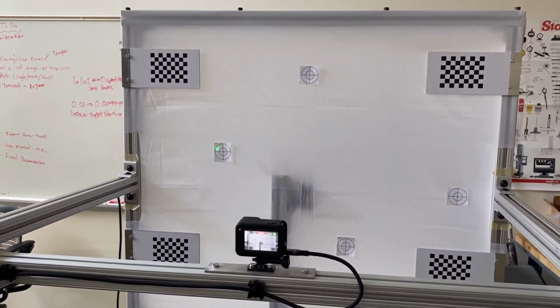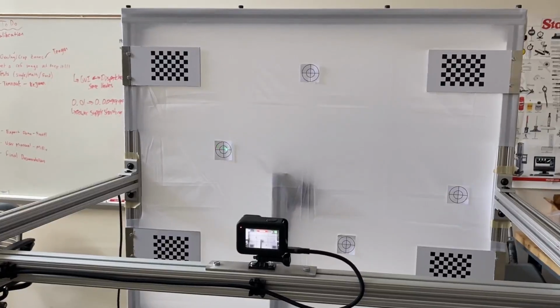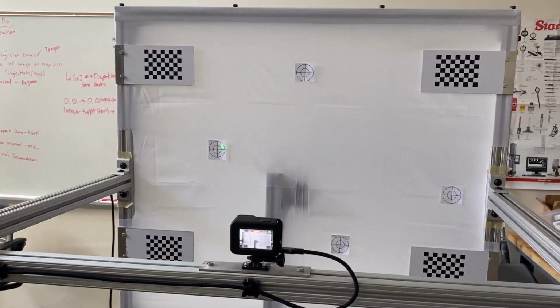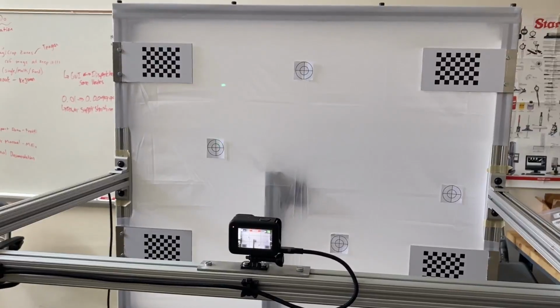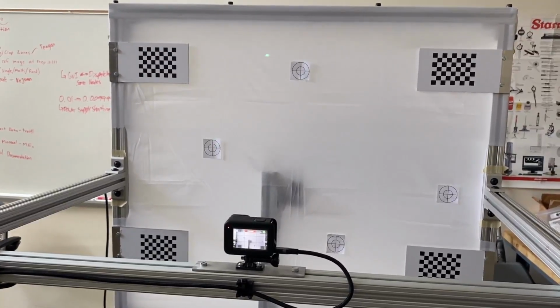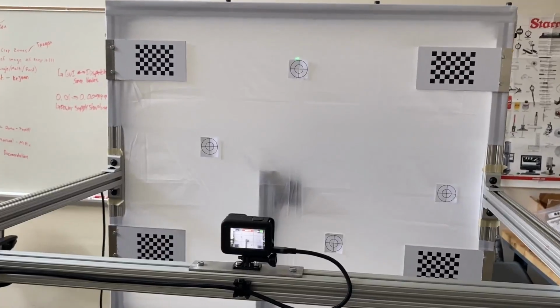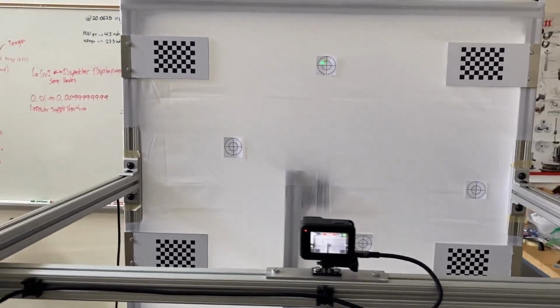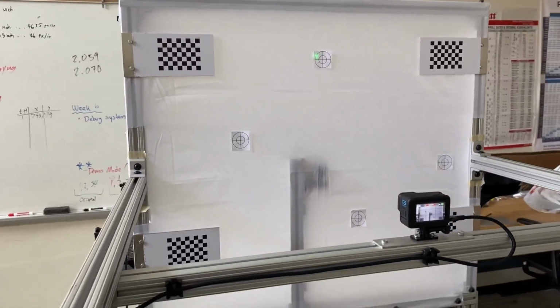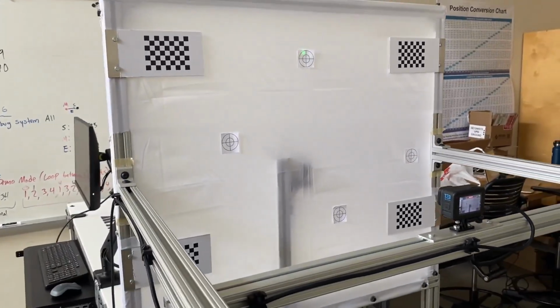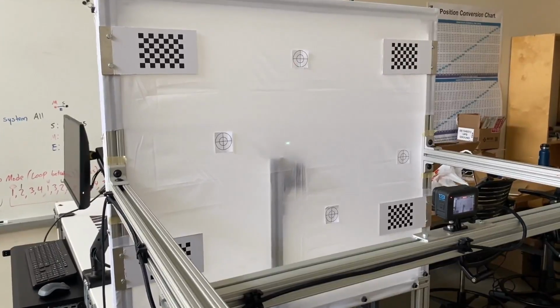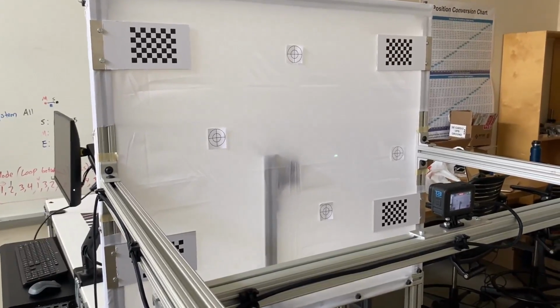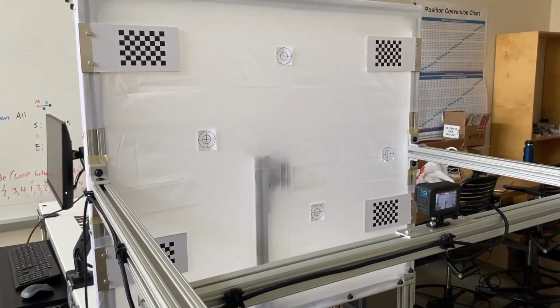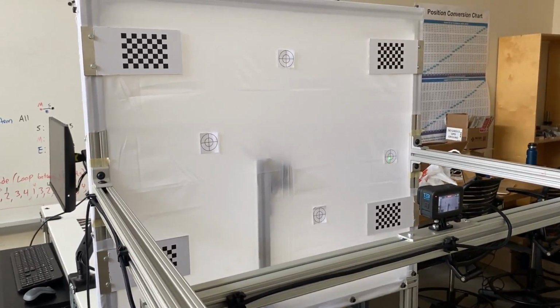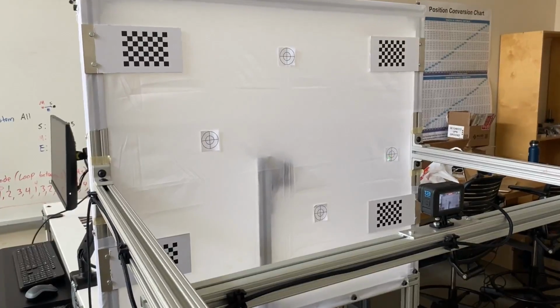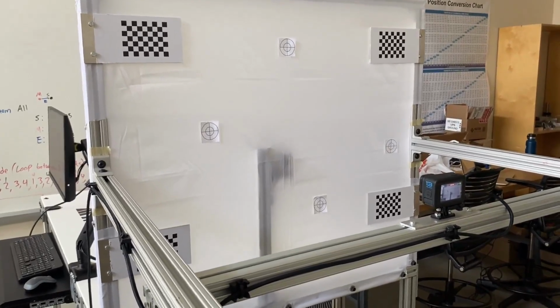Currently, we're running the 4 spec test. As we move to the screen and camera, we can observe that the laser dot is getting to the first 4 targets. In each target, the position of the actuator and the pixel location of the laser related to the position of the actuator are stored. The position of the actuator is represented as vertical and horizontal voltages. Once the laser hits the first 4 targets, the system switches to recall the targets based on the recorded memory voltage position of the actuator. In each recall position, the pixel location of the laser is recorded to then compare with the initial pixel location, allowing us to calculate the angle difference.